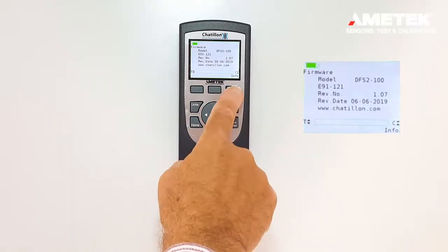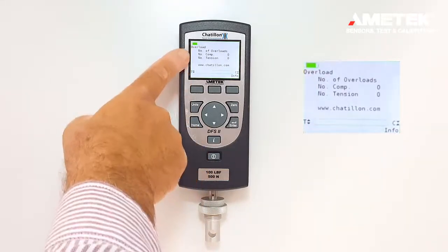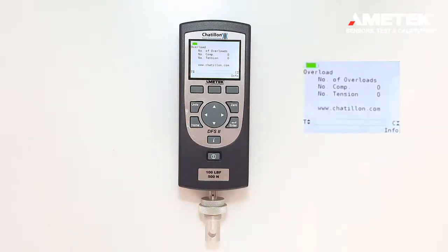Now if the information button is pressed again, we have the number of overloads. Whenever there's a load on the force gauge in tension or compression over 120%, an overload will be recorded either in tension or compression.